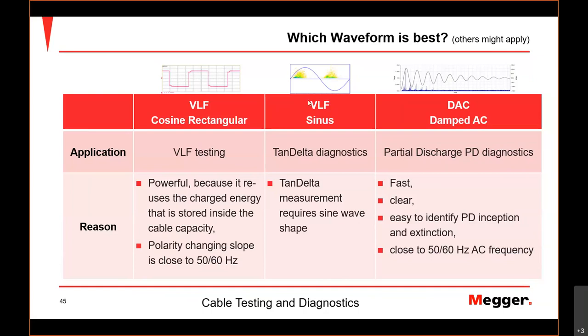But where we do need sine wave VLF is for tan delta measurement. For the tan delta diagnosis, we need to do it with the sine wave, and that's why it's there and it has its place on our list.